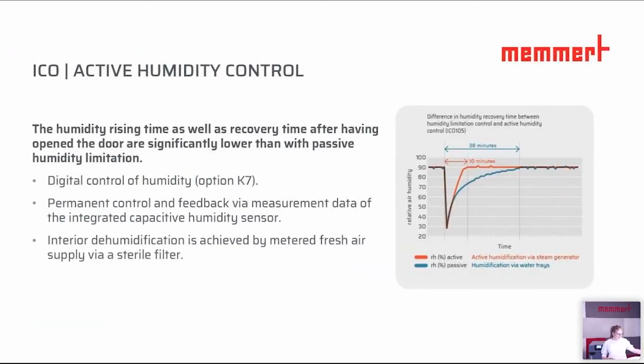Comparing this then to our active humidity control, we notice that we have much shorter humidity rising times and also quicker recovery times after having opened the door. So you will be provided with a digital control, which can be directly set at the control cockpit. This is ordered with option K7. The permanent humidity control is measured by a capacitive humidity sensor inside the chamber, and gives that feedback to the control cockpit for easy viewing at first glance. The dehumidification, on the other hand, is achieved by a metered fresh air pump.